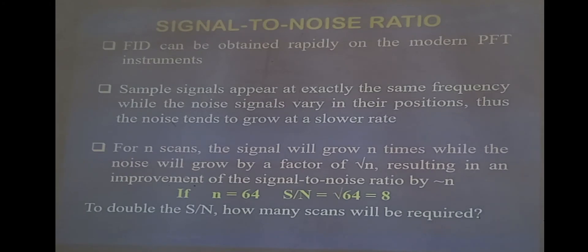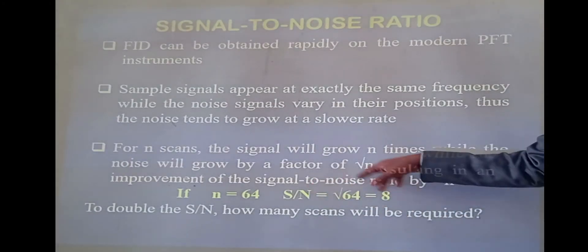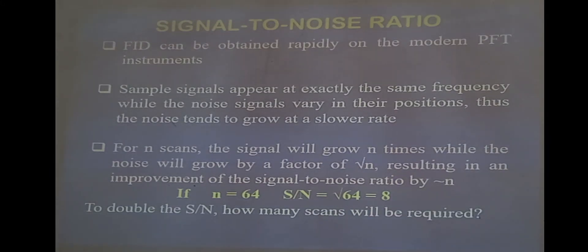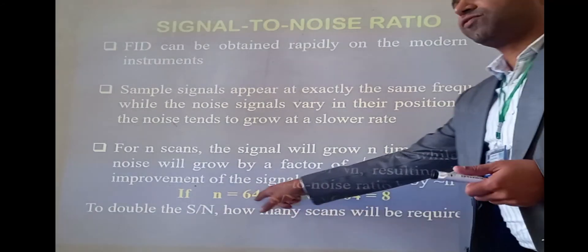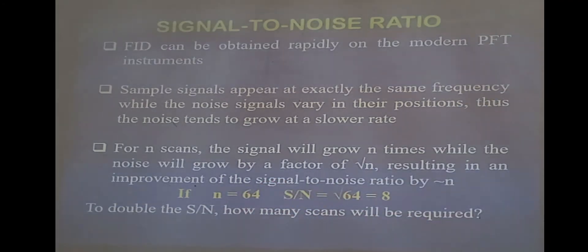So if you have n number of scans and n is equal to 64, then the signal-to-noise ratio is calculated by taking the square root of 64, which is equal to 8. So signal divided by square root of n: 64 divided by square root of 64 equals 8. If n is equal to 64, the signal-to-noise ratio is equal to 8.